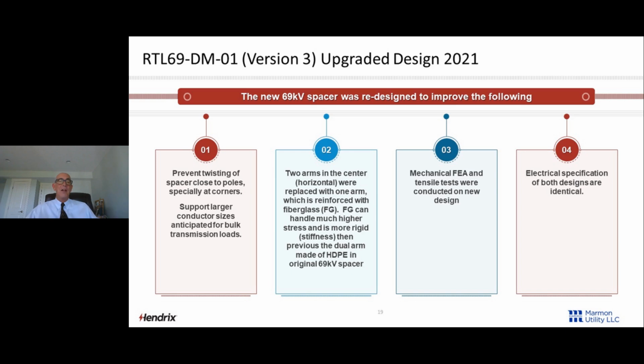The third version just came up 2 years ago. We said, hey, we want to prevent twisting of the spacer close to the poles. We also want to be able to support larger conductor sizes. We're going to be building transmission lines, not with 795 and 954, but at some point 1192, 1350, 1510. So we want to support larger conductor sizes that are anticipated for bulk transmission loads. So what we did is the two arms in the center were replaced by a single arm with reinforced fiberglass. And that reinforced fiberglass can really hold an unbelievable amount of load and compression.